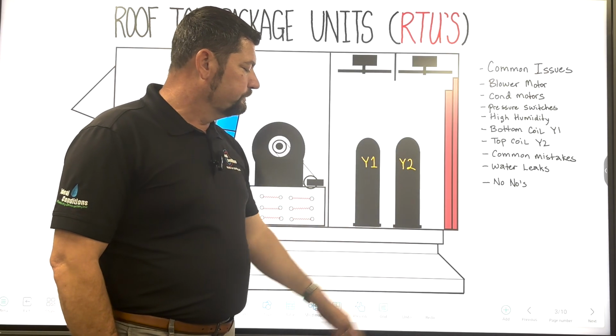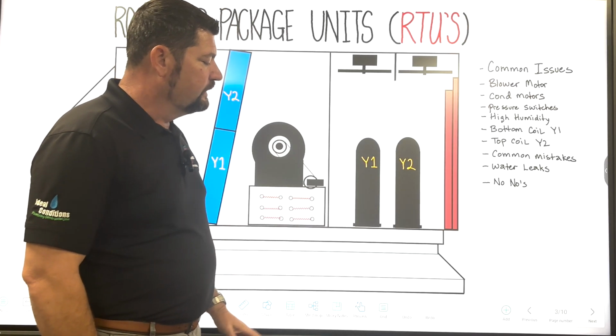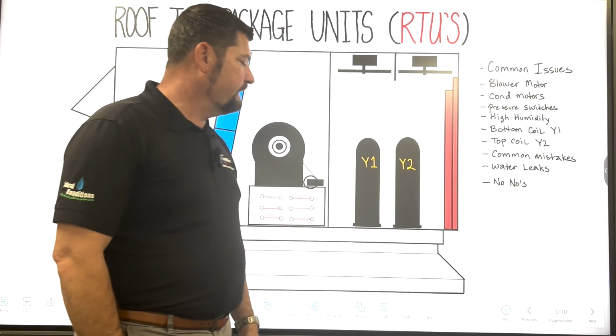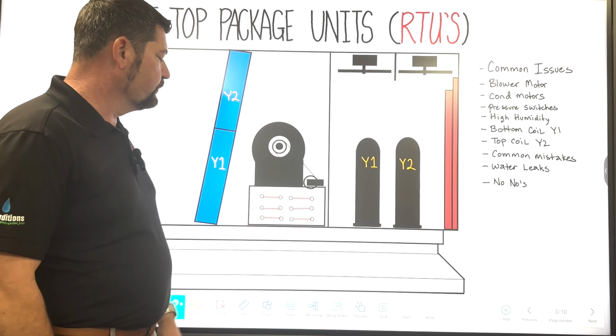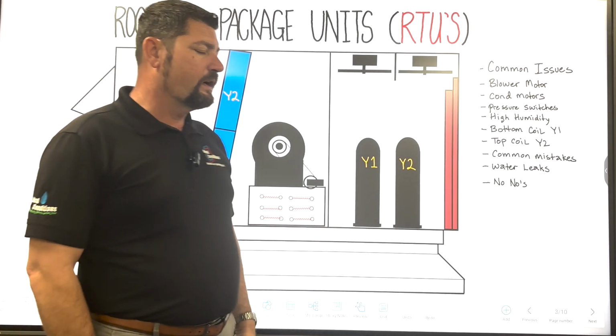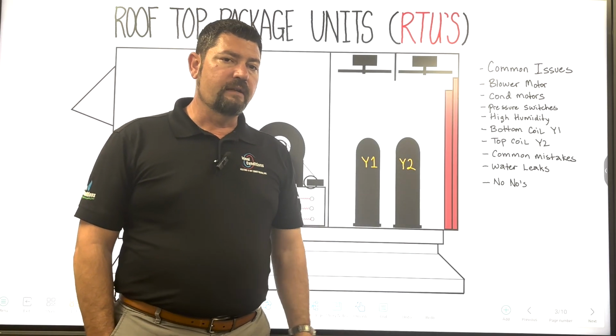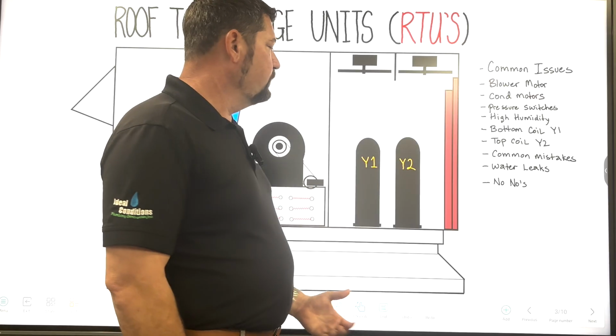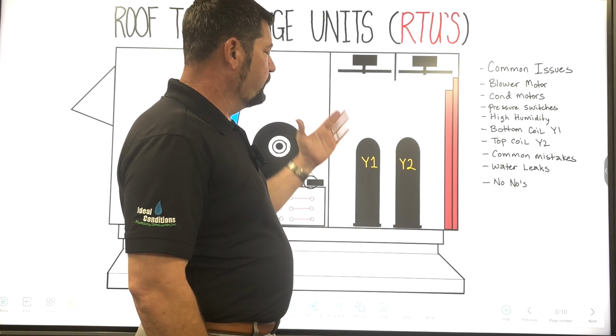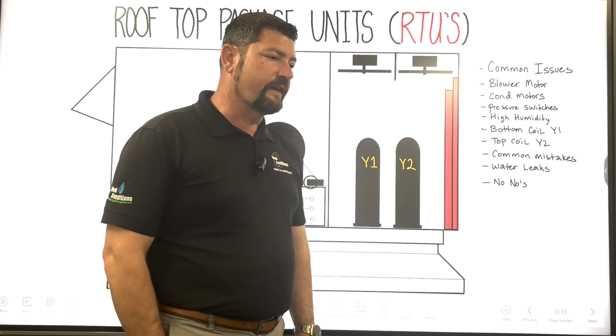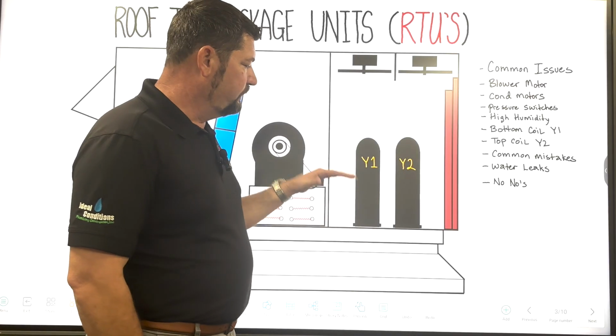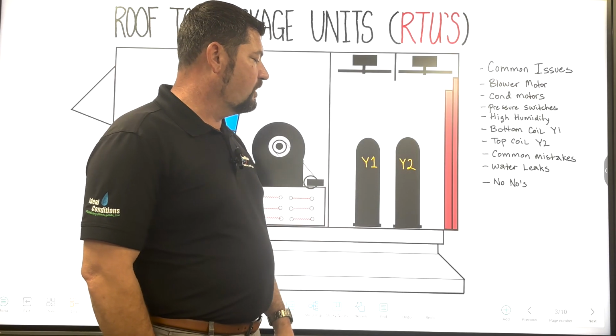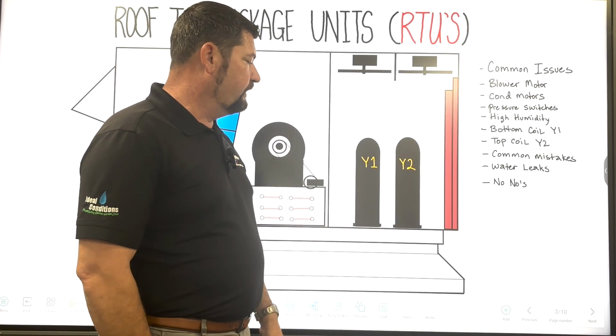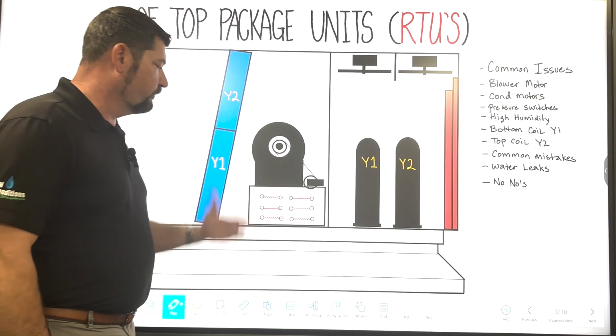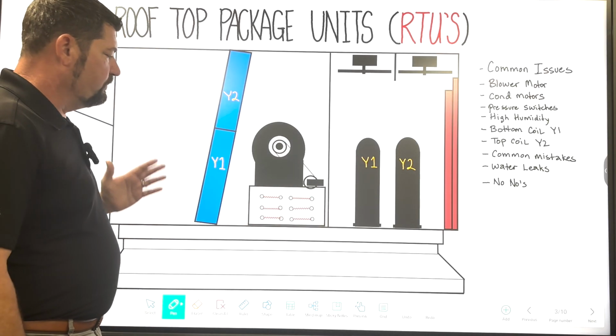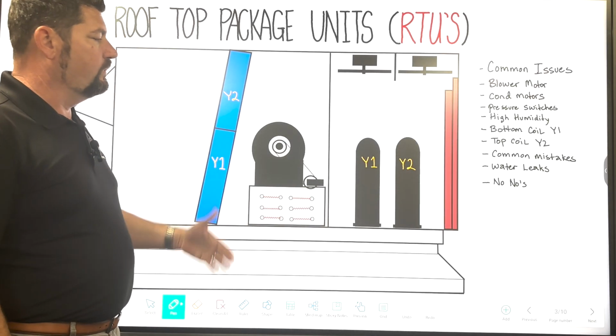These curbs could be leaking. Obviously, the roof itself could be leaking because screws get dropped on the roof deck, and that membrane winds up getting a hole poked in it because somebody's stepping on the screw. Seeing a lot where the panels don't get securely fastened, and then wind comes in and pushes the panel off. Compressors overheat as a result of that, or over here, coils will freeze up. We can go on and on and on.